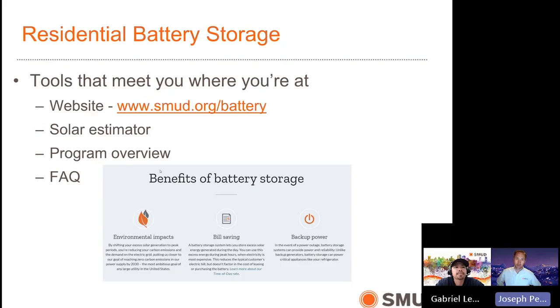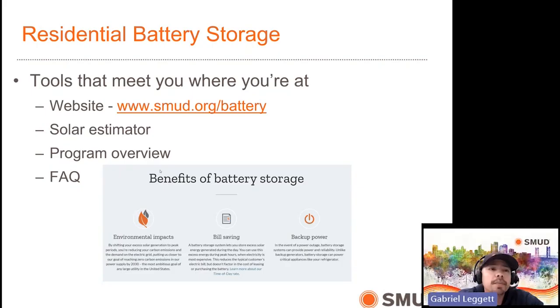With that system, because the microinverters are not multi-port inverters, you won't be able to directly connect your battery's DC side to those inverters, so you can't share them. That would be called a hybrid inverter. You'll need a separate inverter for your battery, and you can keep using your microinverters for your solar system, then coordinate the two. The battery system can sense whether you're sending energy back to the grid or energy is flowing in, and builds in an algorithm to know when to charge and discharge, optimizing your NEM rate to store that energy correctly. But yeah, you wouldn't be able to integrate both together with that system.